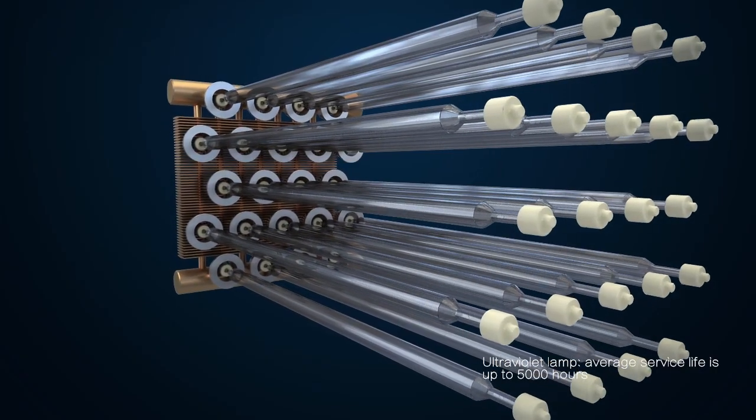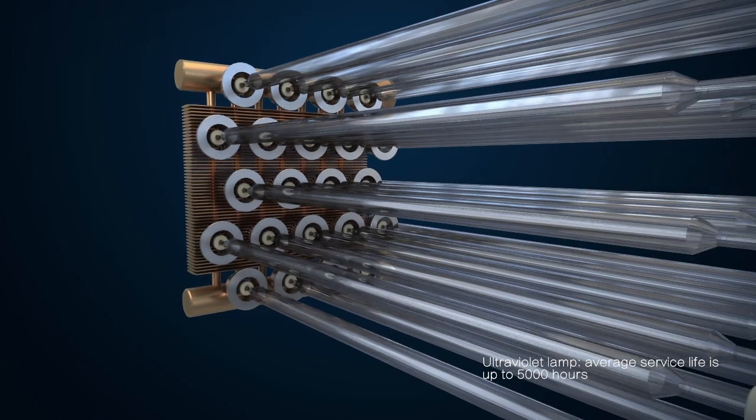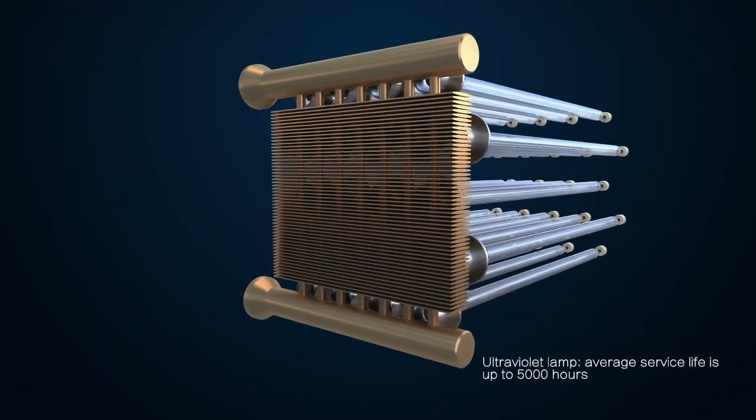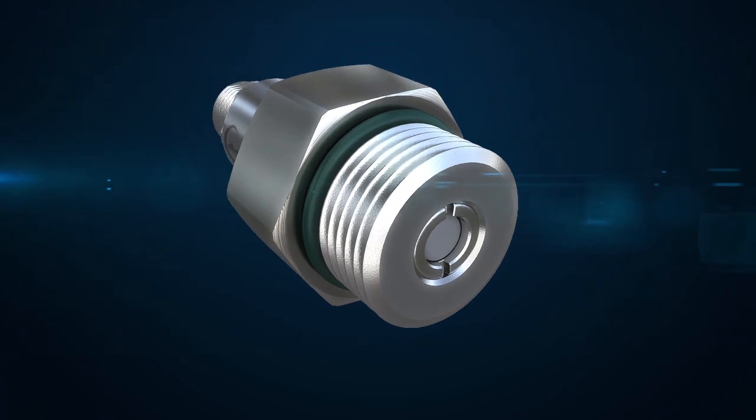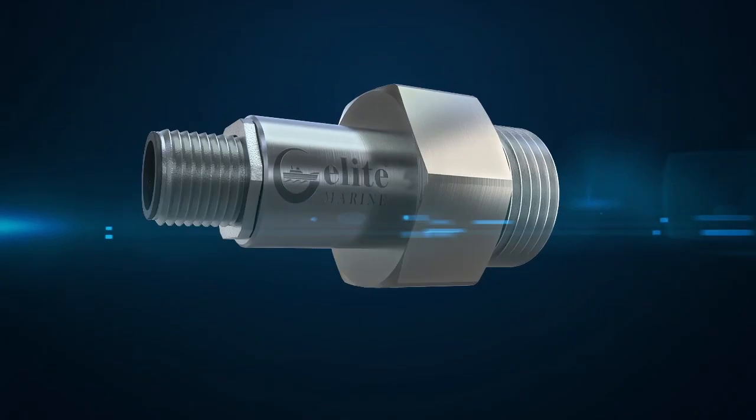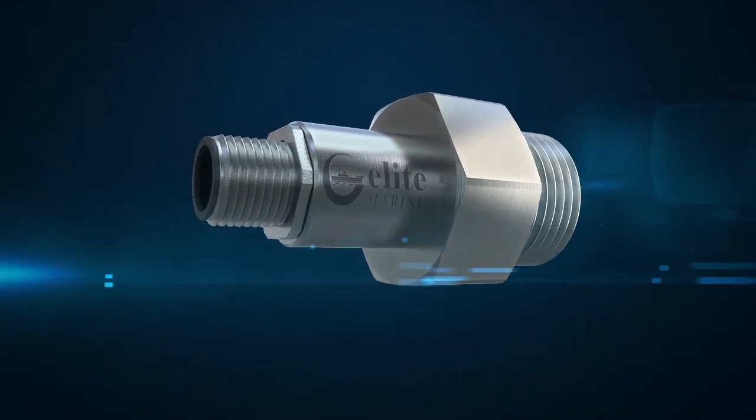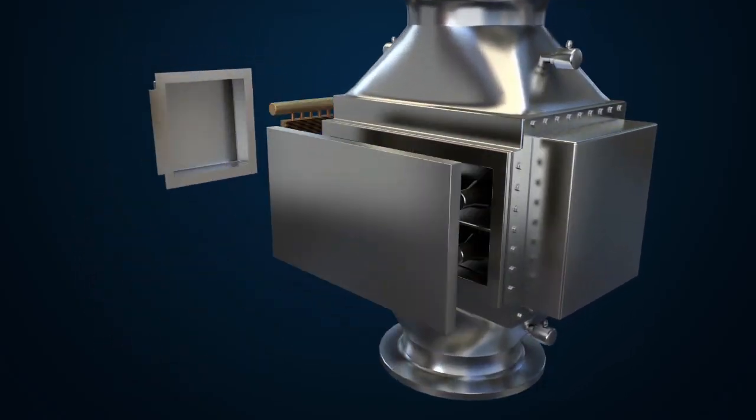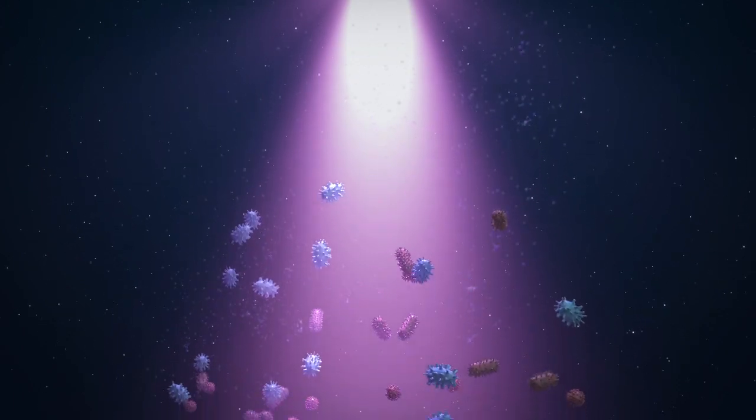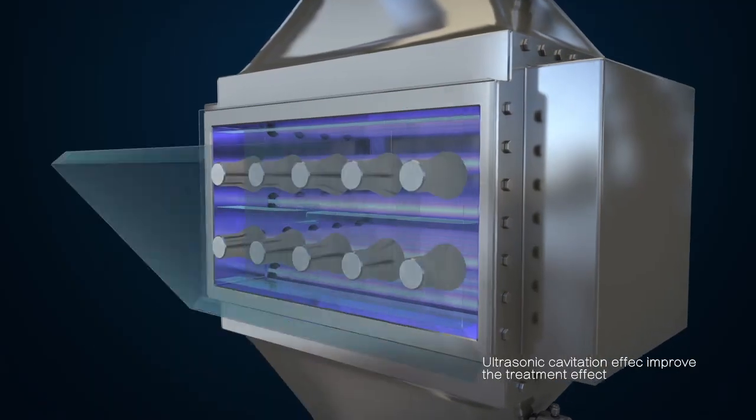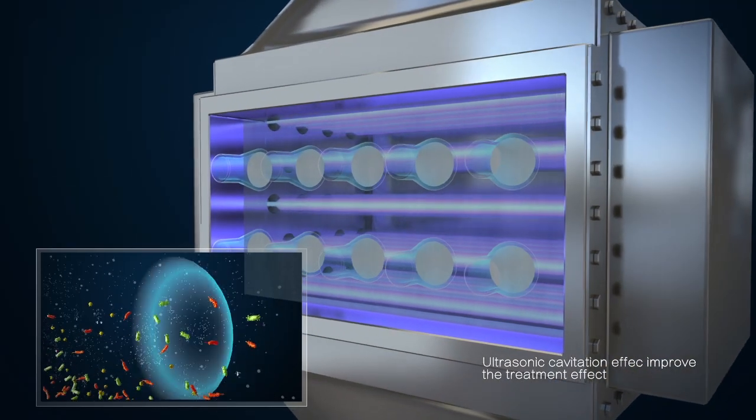The ultraviolet lamp adopts UV C band of high conversion rate and both sides equipped with cooling device. Adopt UV sensor to detect the transmission in order to adjust the output power of UV lamp. Ultraviolet radiation can destroy biological genetic material and kill organisms. Ultrasonic cavitation action also improves the treatment effect.